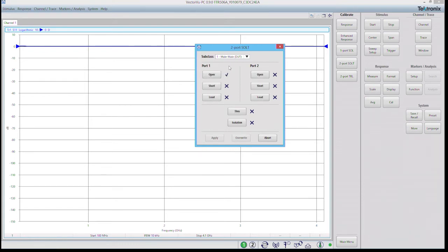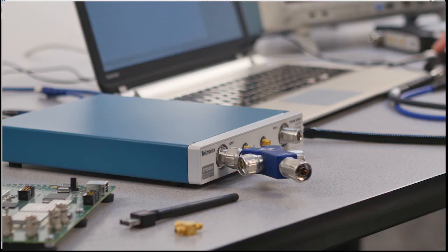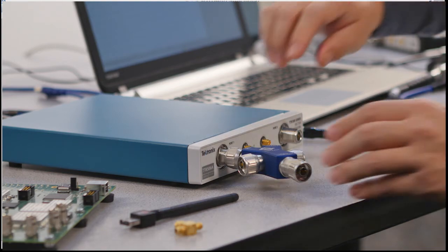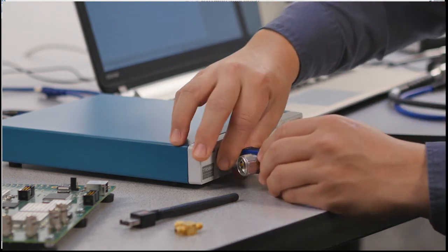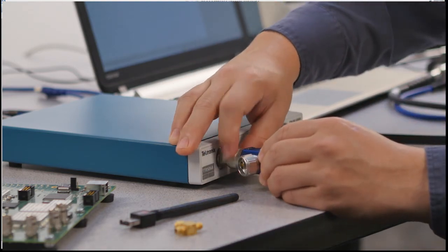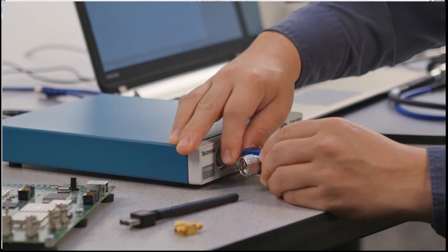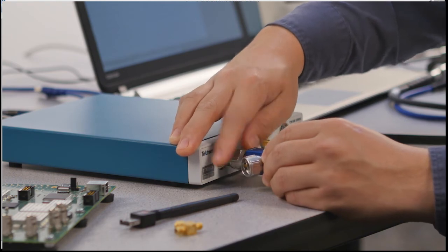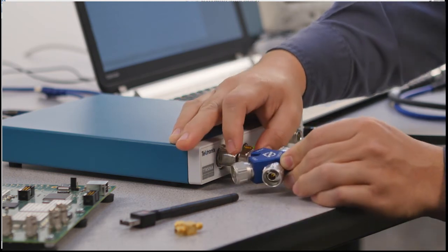I will repeat this procedure exactly the same for short and load. So unscrew the open, screw on the short.